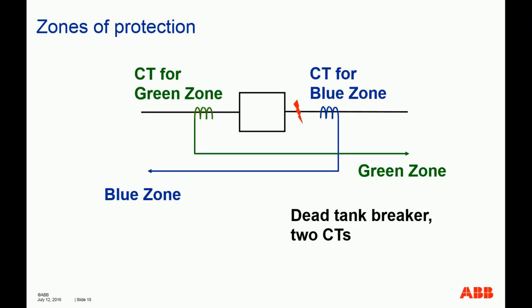In a typical, for example, main tie main scheme, if you consider this as a tie breaker in the middle, typically in a switchyard you would order or specify CTs across the breaker like this, so they overlap each other. The advantage of this is there will be no blind zone. Any fault here in the middle will cause the bus protection, I'm talking about the blue zone on the left and the green zone on the right, to operate at the same time simultaneously. So basically there will be no blind zone.